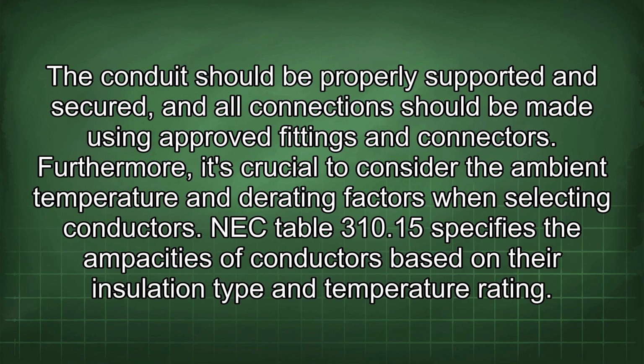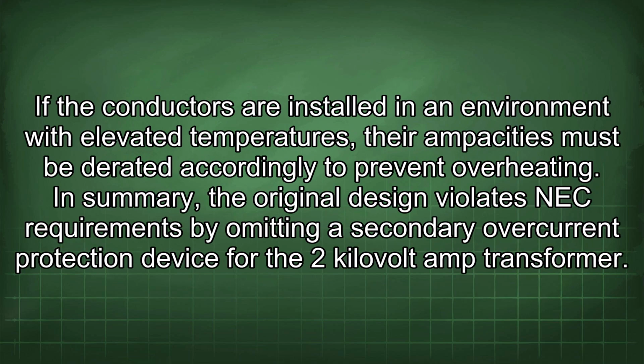The conduit should be properly supported and secured, and all connections should be made using approved fittings and connectors. Furthermore, it's crucial to consider the ambient temperature and derating factors when selecting conductors. NEC Table 310.15 specifies the ampacities of conductors based on their insulation type and temperature rating. If the conductors are installed in an environment with elevated temperatures, their ampacities must be derated accordingly to prevent overheating.